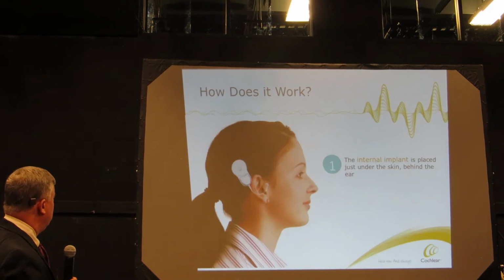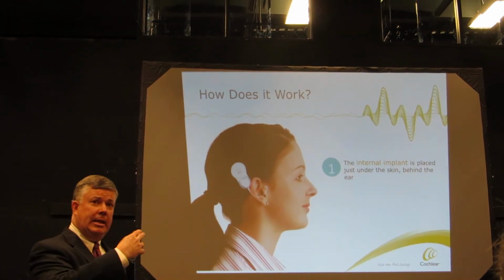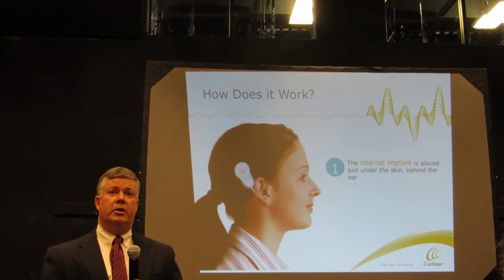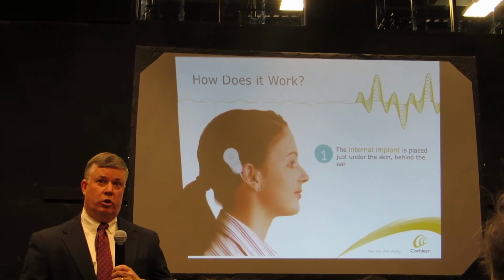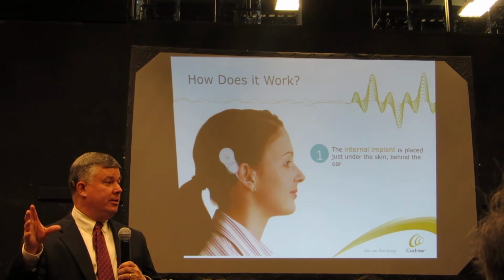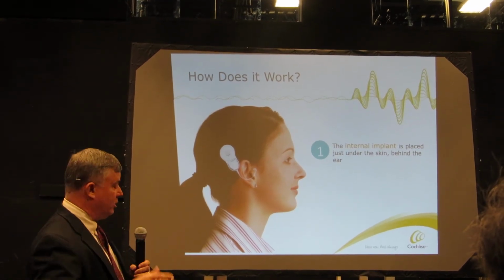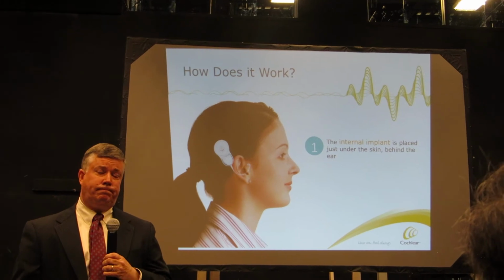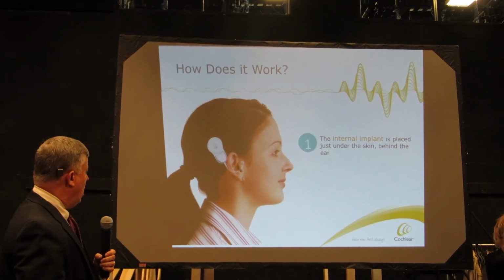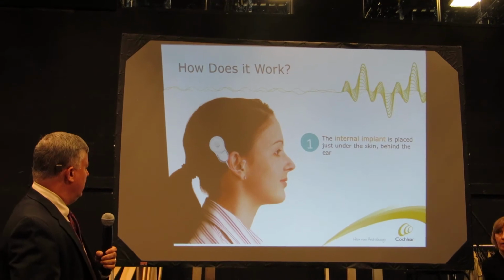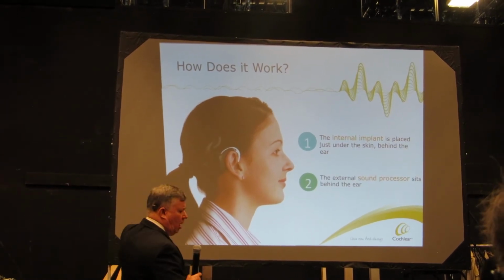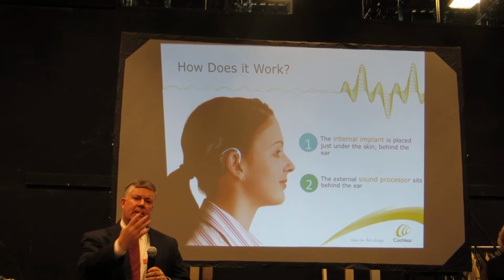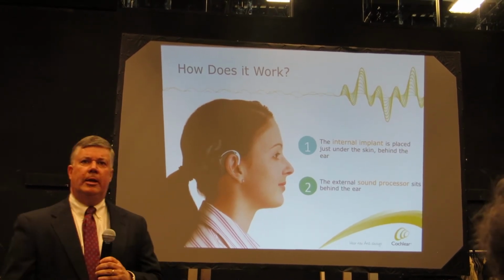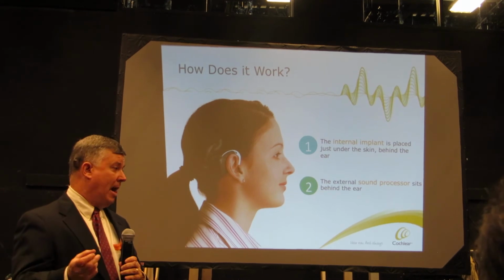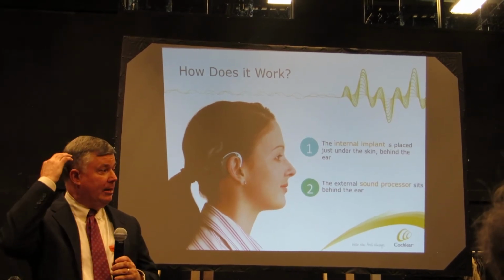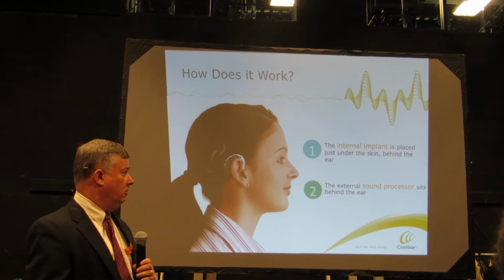How does it work? The internal part of the processor is placed under the skin. What you're looking at now is through the young lady's hair and skin underneath. It's implanted against the skull. You can see the two wires going down underneath and into the cochlea. Then the external processor is put over the ear, and the two are connected by way of a magnet: a magnet on the inside and a magnet on the outside at the end of the coil.